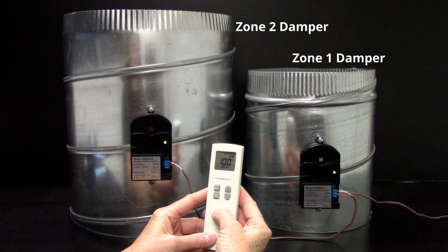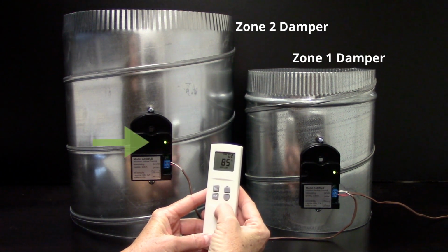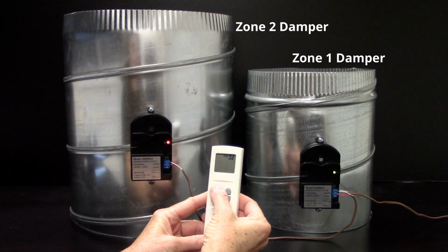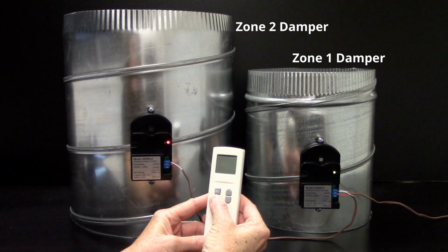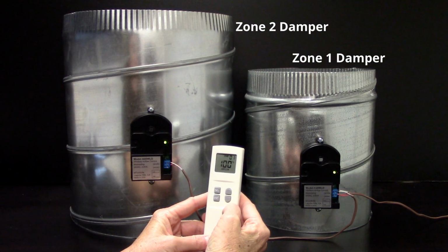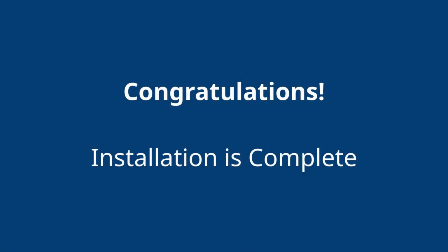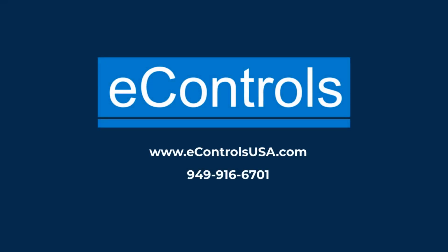Test the damper operation in Zone 2 by lowering the airflow. You should observe the green and red LEDs alternately blinking on the Zone 2 damper. Zone 1 damper should still be displaying a green LED. To control a different zone, simply press the Select key, use the up or down key to select the desired zone, then press Enter. Congratulations! Installation is complete. If you have any questions regarding the WRCD wireless remote damper control, please contact us.